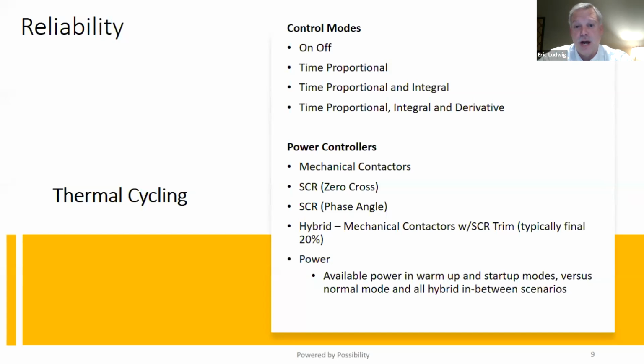And then you have your actual power switching devices, the devices that are turning on and off the actual power going to those resistive elements. Those could be mechanical contactors or what we call an SCR. There is an SSR as well, a solid state relay, but at the amperages that these are pulling, those typically don't come into play.